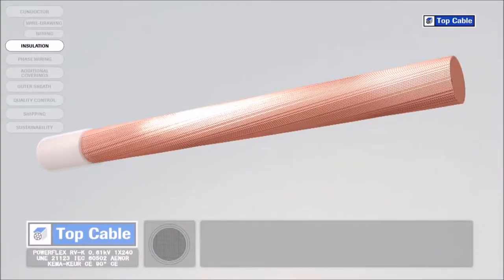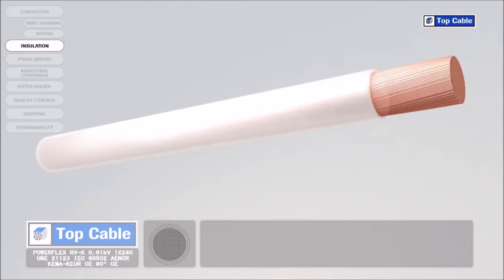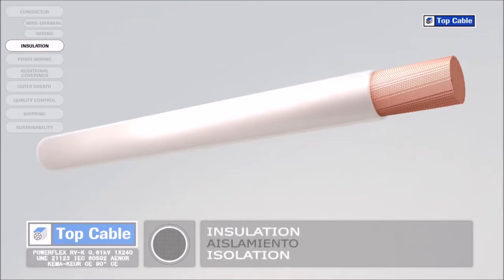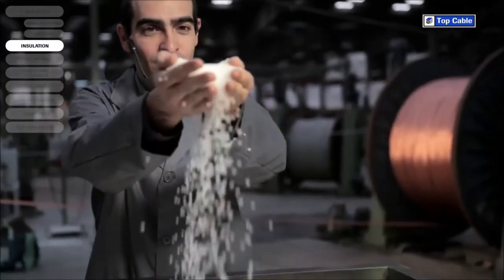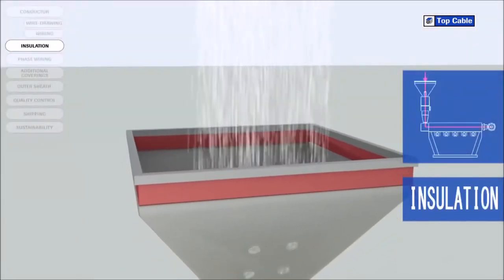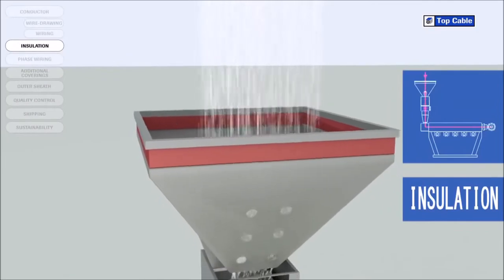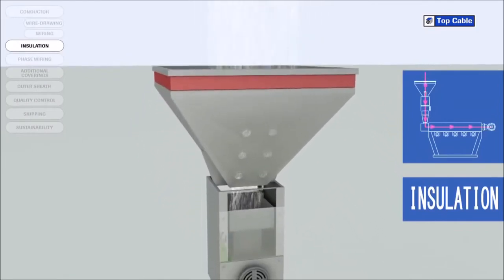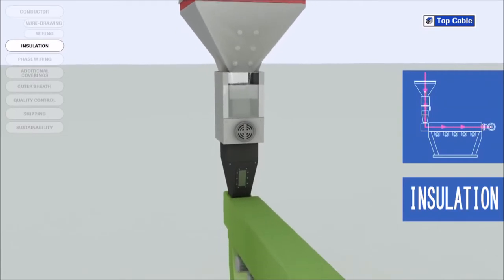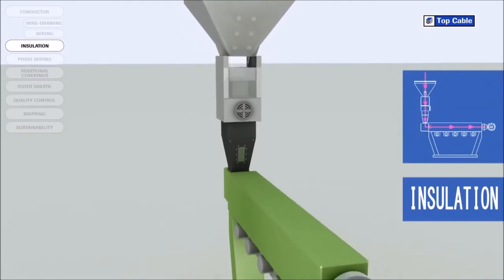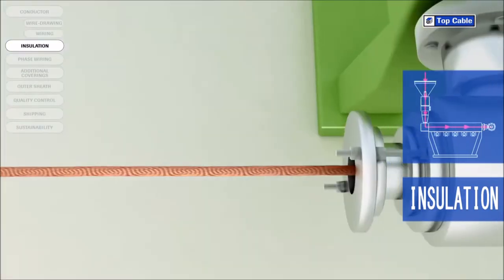The next process in the manufacture of electrical cables is the insulation. This is when we place an insulating cover over the conductor to prevent current leakages. In this process, the insulating material is added by a process of extrusion at high temperature. The insulation ensures there are no current leakages. Several insulating materials may be used — PVC, EPR, XLPE, etc.